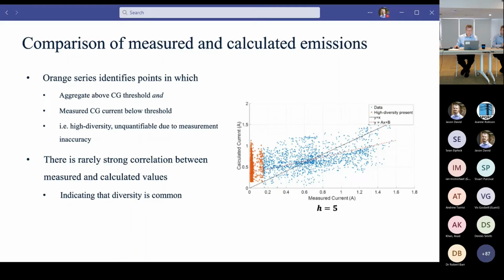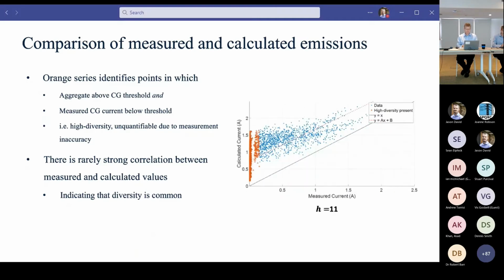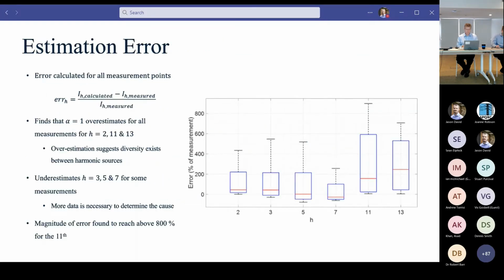This ultimately identifies that diversity is quite common, even at characteristic harmonic orders such as the fifth. This sort of analysis was performed across all harmonic orders, particularly those with valid measurements. As you can see here for the 11th, every single measurement overestimates the assumption that phase angle diversity is 0.